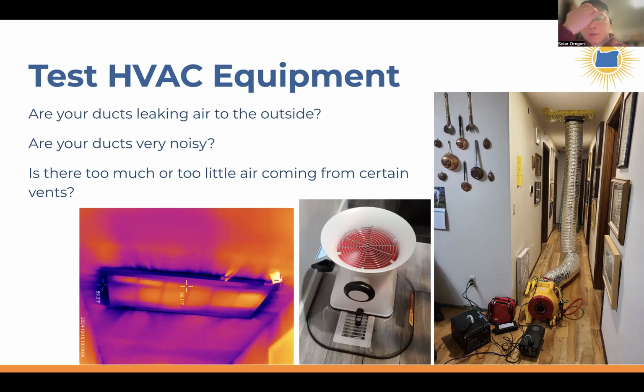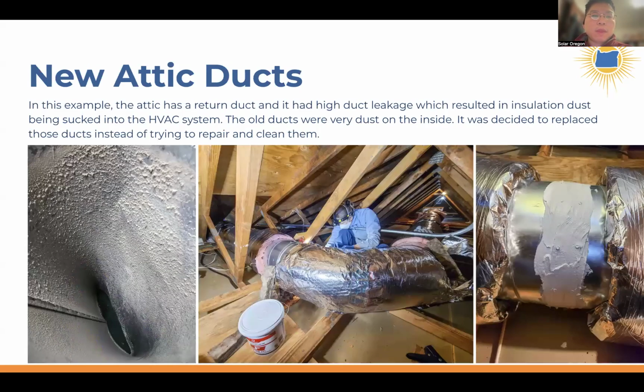So this is really important testing to figure out what sort of duct corrections are needed before an attic or a crawl space gets insulated and air sealed. In this example home, the ducts in the attic are not supply ducts, but just the return duct, and the return duct had duct leakage. And of course, you saw in that earlier photo that this home had blown-in insulation in the attic.